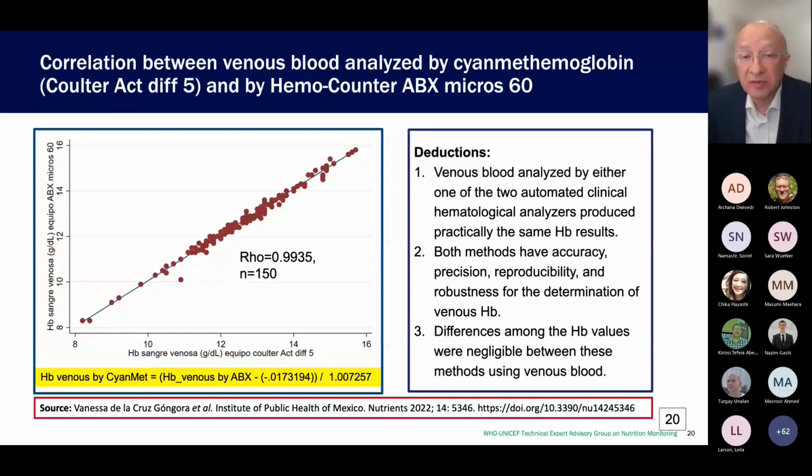The coefficients of variation of these different samples, analyzed only once, was less than 2 grams per liter, really precise results. The slope is 1 and the intercept is 0, which means that the two methods were equivalent. Now we have a gold standard to compare the results that we can get from the HemoCues. The next slide, please.